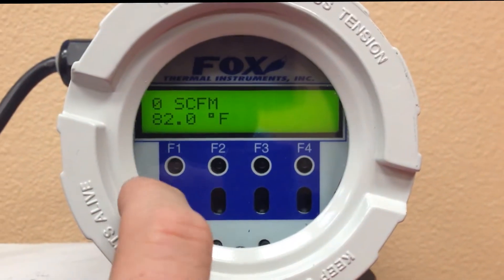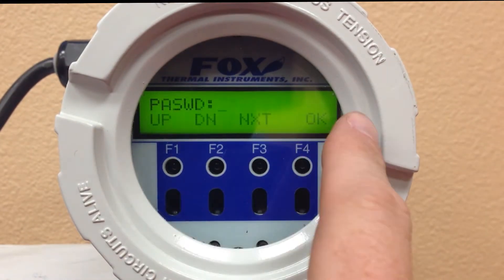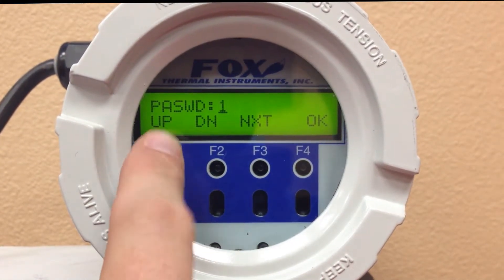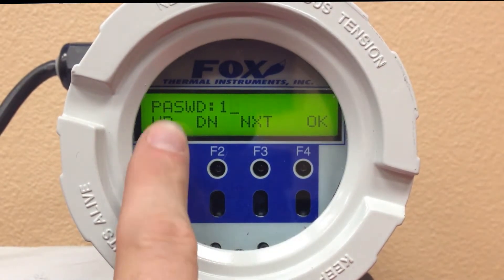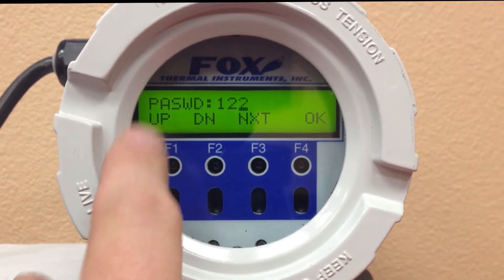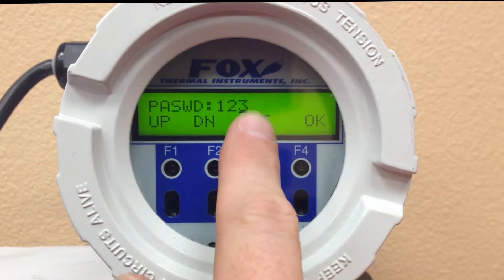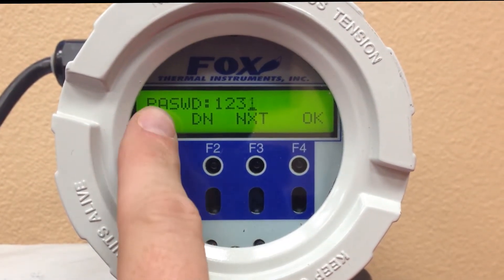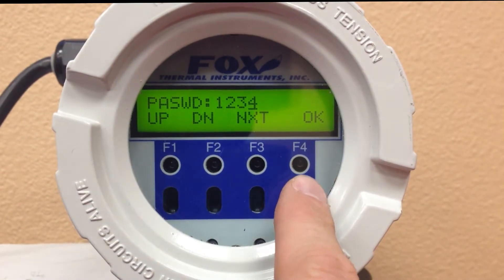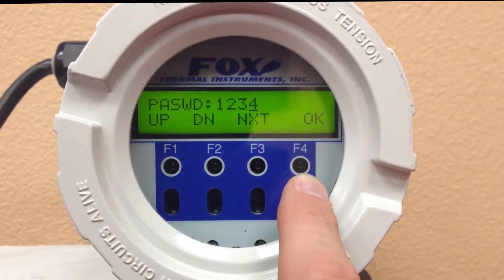So from display one, which is the startup, if we hit it once it's going to say 'set parameter.' If we want to make changes and go to programming mode, we say OK, then hit one, two, three. The IR interface with the wrong lighting conditions can sometimes take a little bit longer, but it's still great for keeping it rated for the hazardous area you're in.